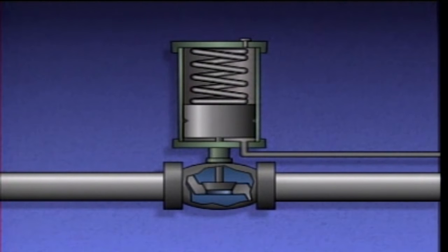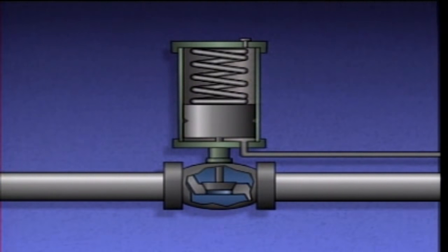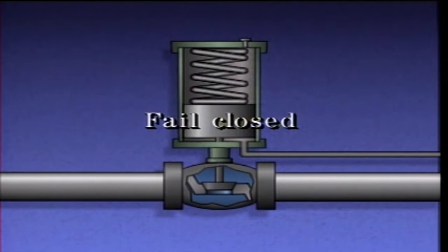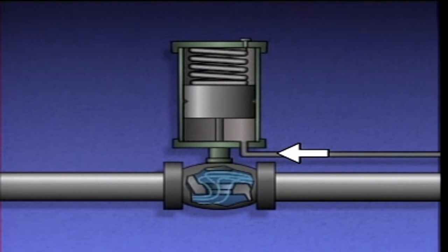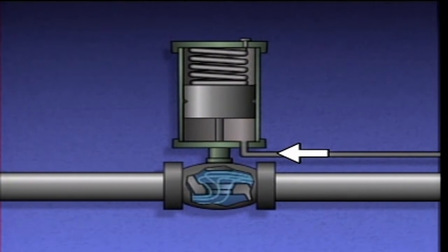If air pressure drops below a predetermined value or is lost completely, the spring will force the piston down to close the valve — the valve will fail closed. Since air pressure is only fed to one side of the piston, this type is called single-acting.